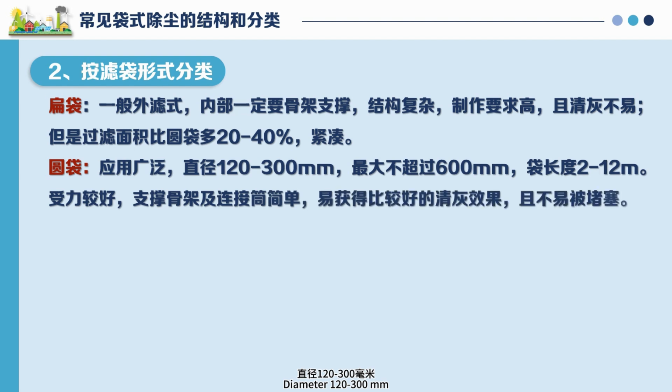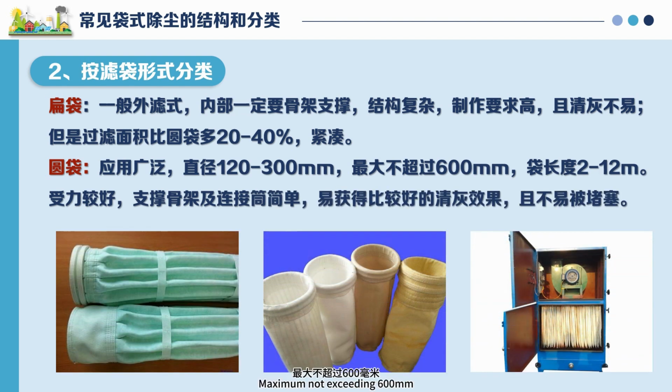Diameter 120 to 300 mm, maximum not exceeding 600 mm. Bag length 2 to 12 meters. Well stressed, with a simple support framework and connecting tube. Easy to achieve a good cleaning effect, and not easily blocked.